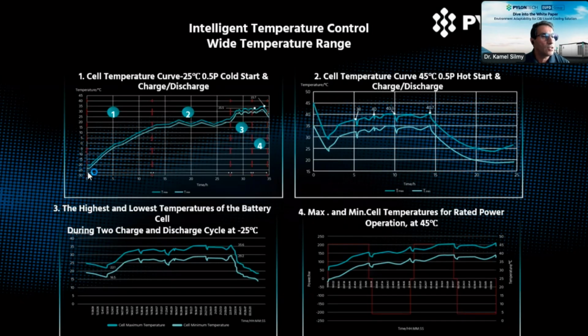We started the system with -25 degrees Celsius. We started with a power of 0.5. We started with a cold start, and then we make a charge and discharge. So what happened actually here? We started here during the cold start phase. This is phase number 1 here. The lowest temperature of the battery cells increased from -25 degrees Celsius to above 10 degrees Celsius, and we need about 11 hours for this.